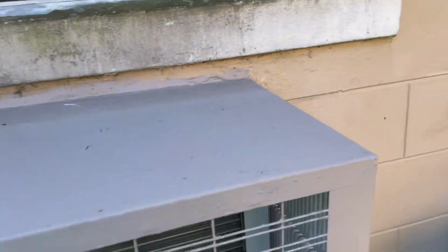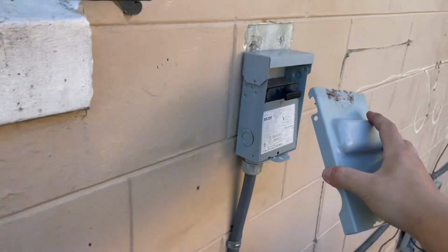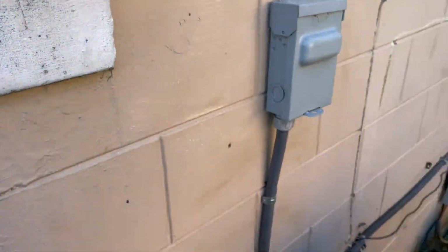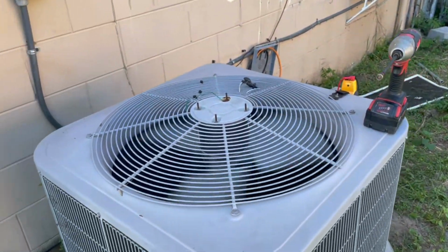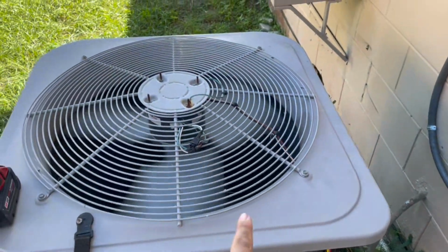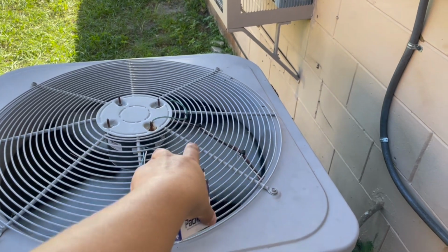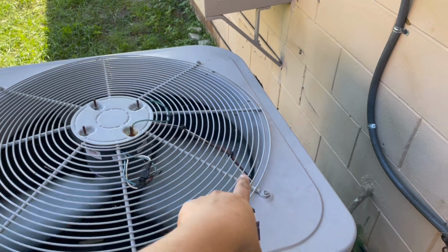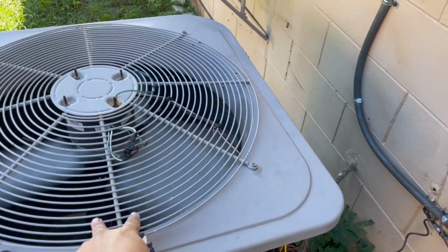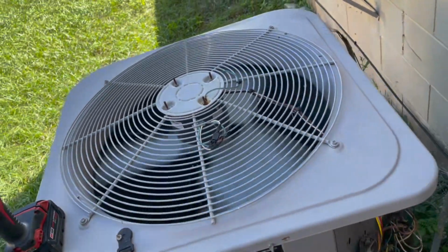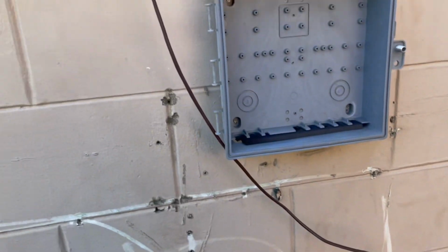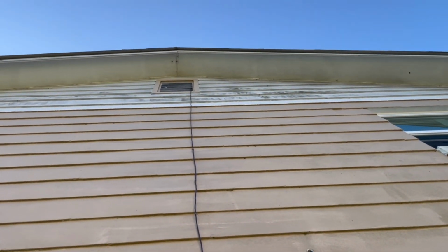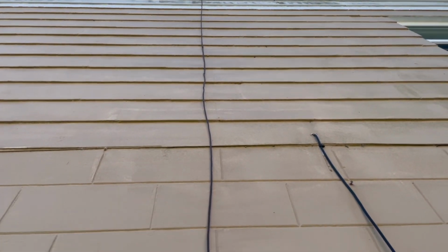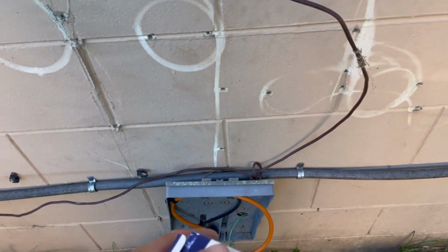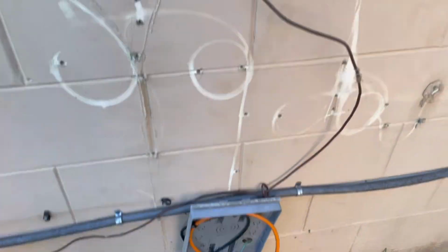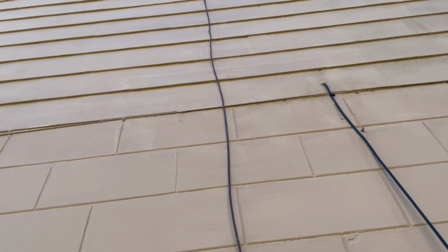I'll go talk to him about the other unit. I think he said he's gonna want me to try and leak search it to find the cause. And, you know, we'll see. And real quick, this is the first time I've seen someone not just reuse that little jacket that comes to cover up the wires for the condenser fan motor. They just strap the wires to the top here. That's crazy. And then they got this thermostat wire going all the way up into the attic. That's crazy. That's something you do just for temporary. You don't leave it like that. Apparently you do.